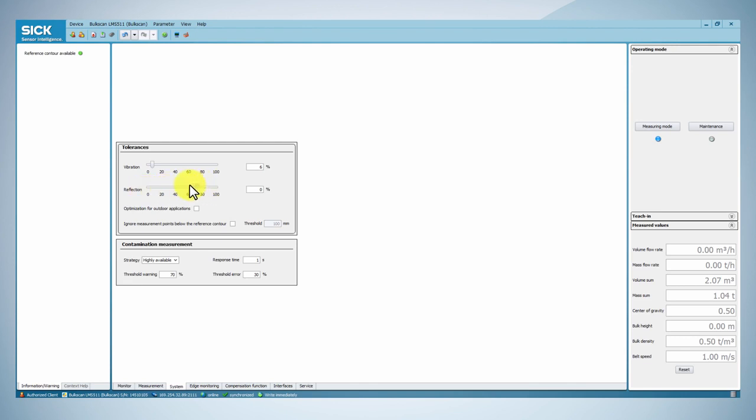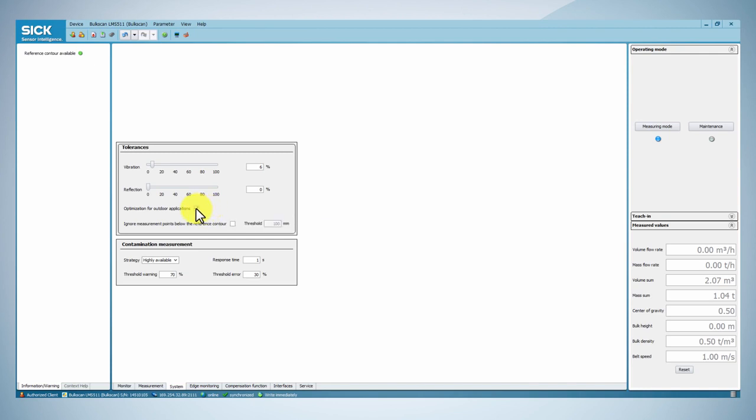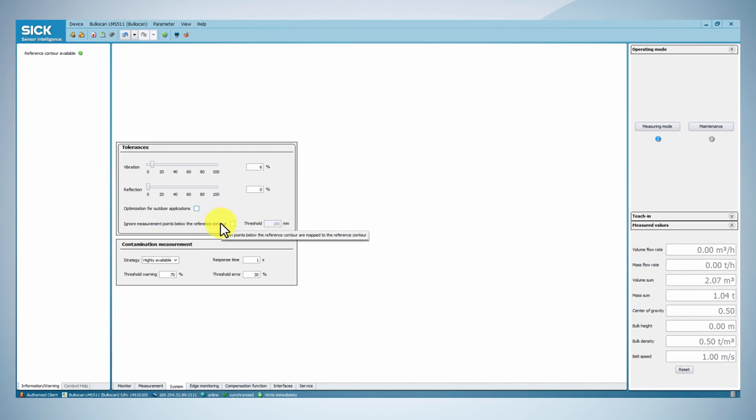Reduce or increase the tolerance against reflection so that the reliability of the system meets your requirements. If you expect external effects such as dust or rain, snow or sunshine reflection on metal surface in your application, you can activate the optimization for outdoor application function in order to avoid invalid measurements.